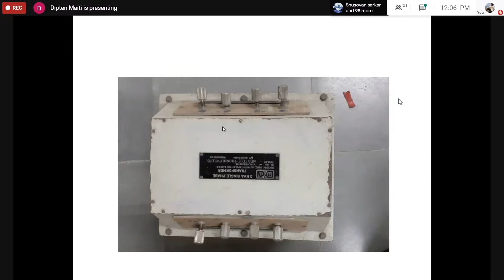There is a box, and this is claimed to be a transformer. We have to test and find whether this is actually a transformer, whether this conforms to the nameplate rating written over there, and then we would try to use the transformer depending on certain extra requirements, or make some circuit connections using the transformer to modify something about it without going into the transformer itself. So the problem is that we cannot open that box to find what is inside. We are just given with this, and we have to test from the outside and justify the nameplate rating, or I would say nullify it.